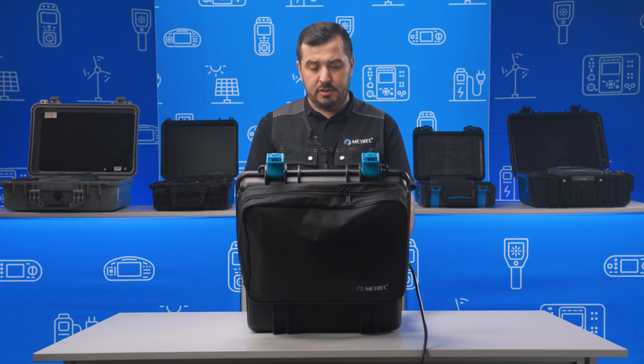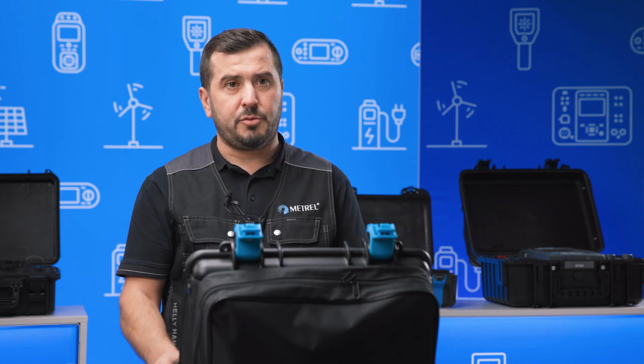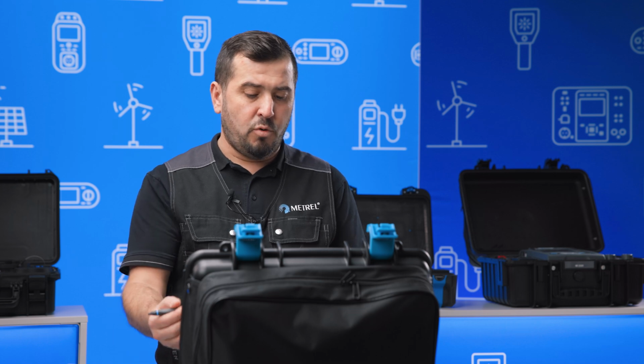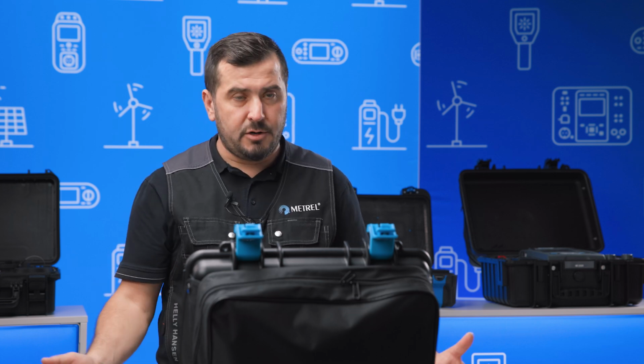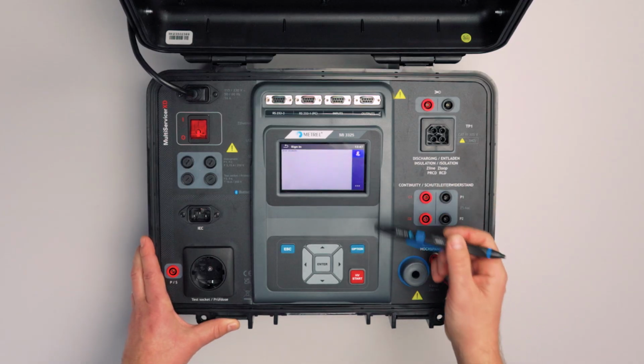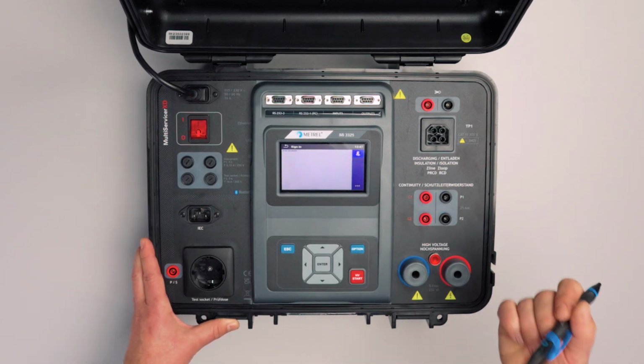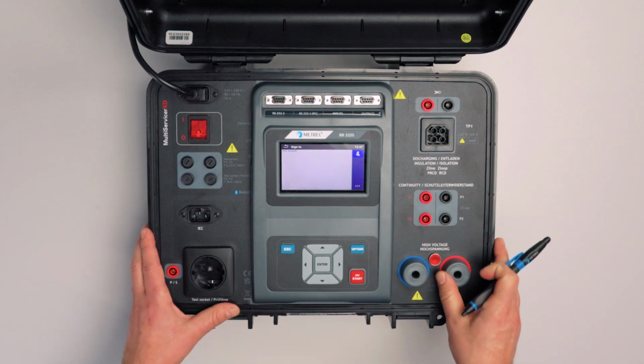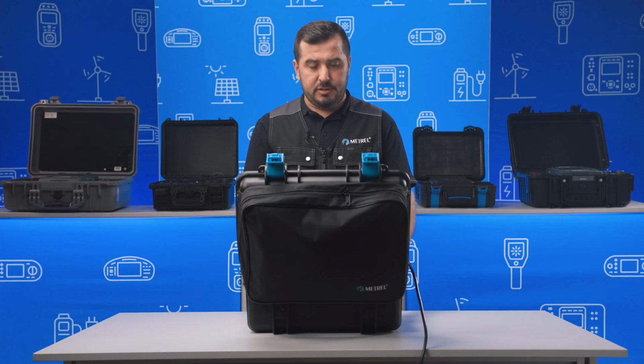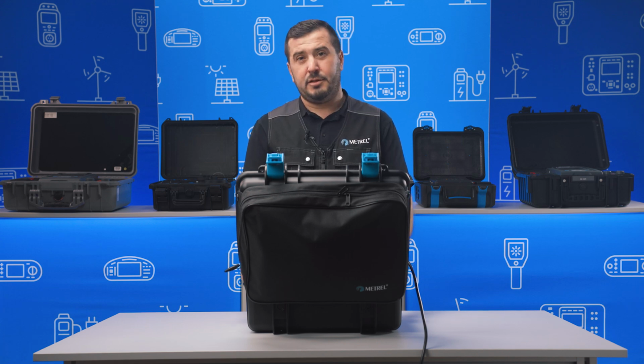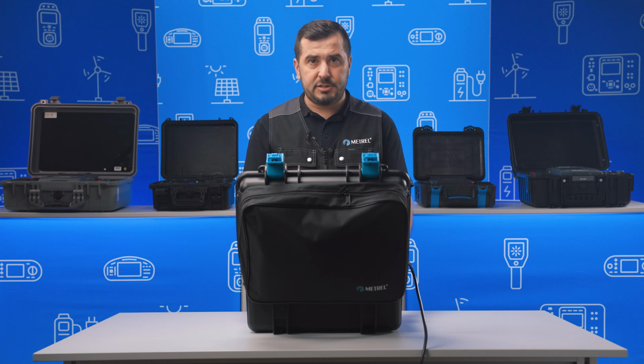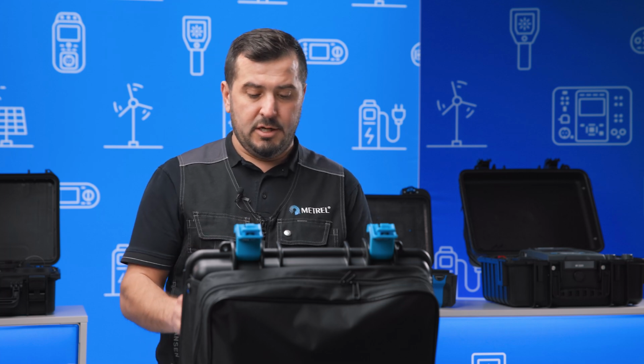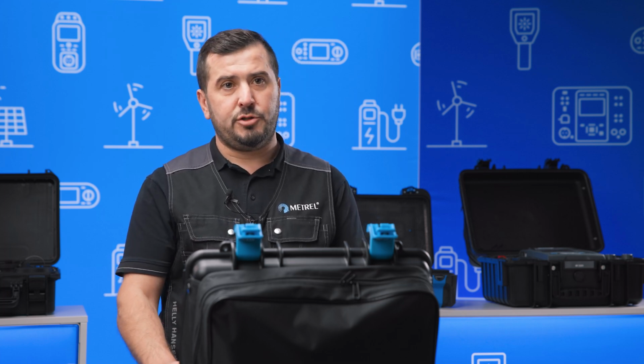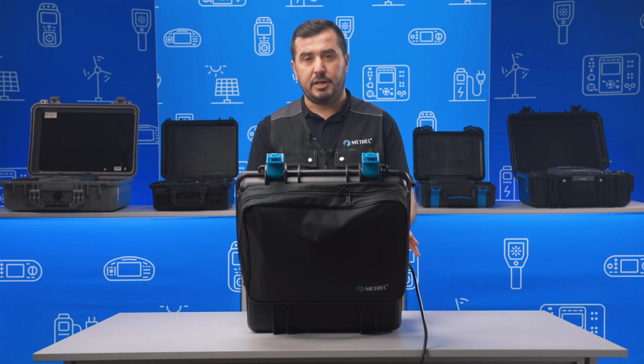Then the user accounts menu. This one is also very important because the administrator of the instrument can assign several different accounts, and each of these accounts can have a username and of course also a password. Again, why is this important? Firstly, the person who does not have the password cannot access the instrument, and the second one, which is more important, is that if we log into the instrument, each particular measurement will be signed with the username.